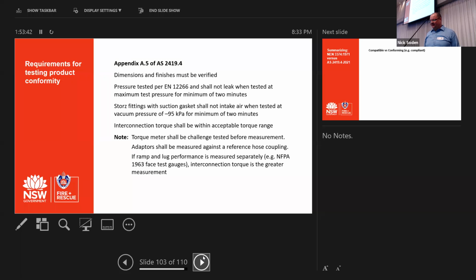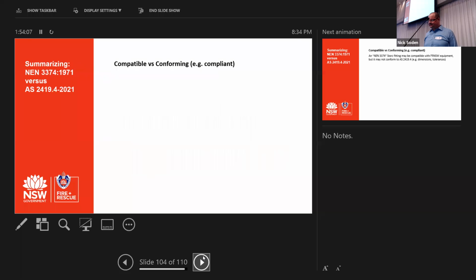And if the ramp or lug performance is being measured separately, which is described by NFPA testing or Canadian CAN testing, then you must use a face test gauge. And then the torque, whichever measurement is greater, is the interconnection torque. So you'll find that 125, 150, etc., are actually done to NFPA standards and not to DIN standards.